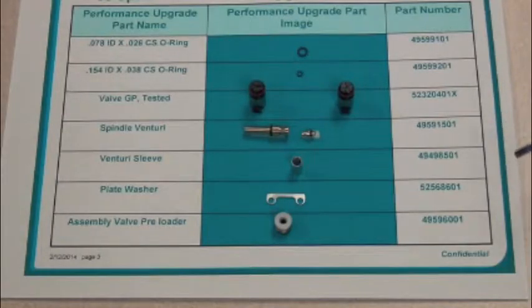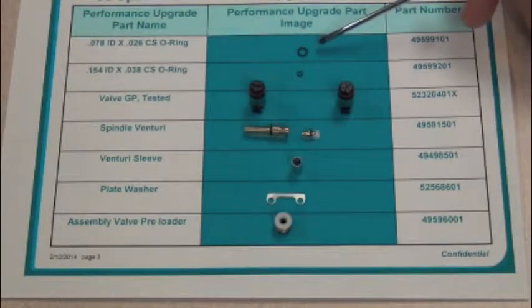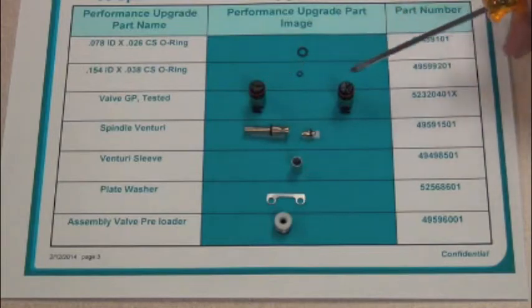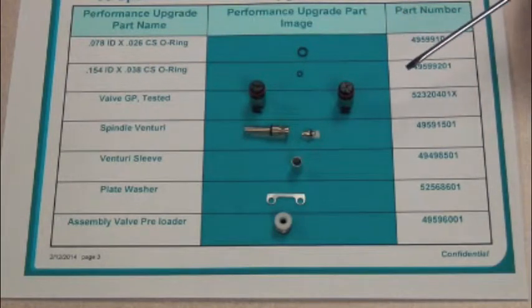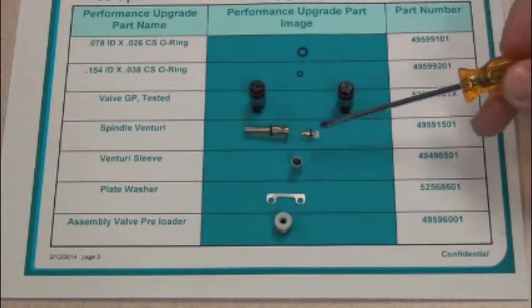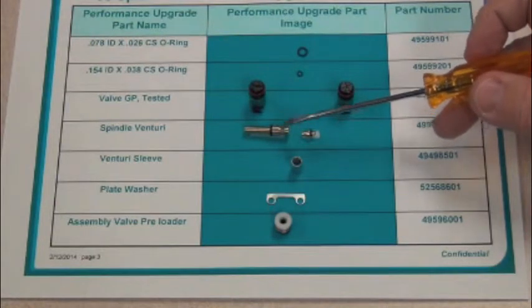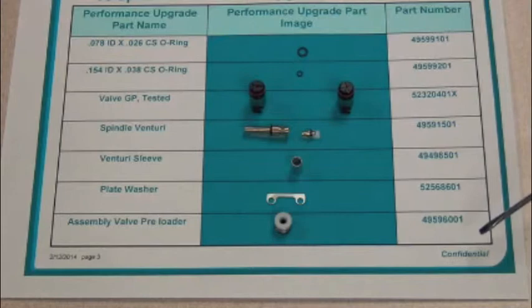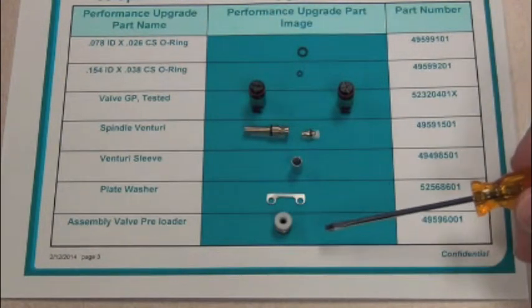The parts required for the spindle performance upgrade are one large o-ring, one small o-ring, two poppet valves, one venturi with o-rings (a large o-ring and a small o-ring), one venturi sleeve, one plate washer, and one valve preloader.